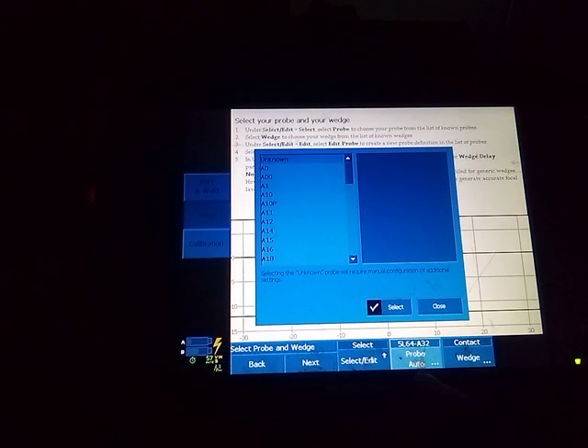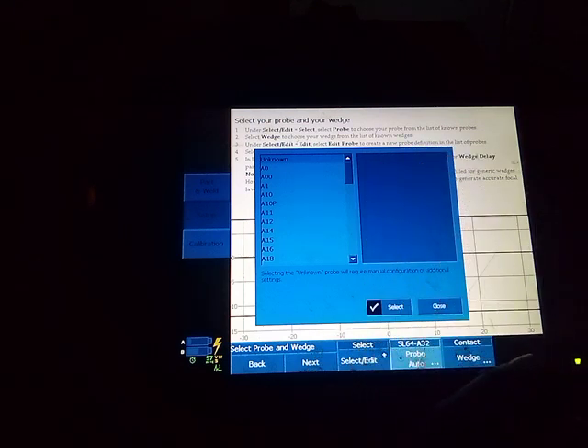here is our probe. It has already been detected. If not, you will take the probe, and it will be written on the probe, so you should be able to know the name of the probe in case the machine did not detect. But our machine has already detected. So now here we are going to select our wedge.